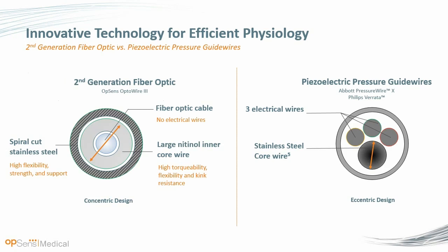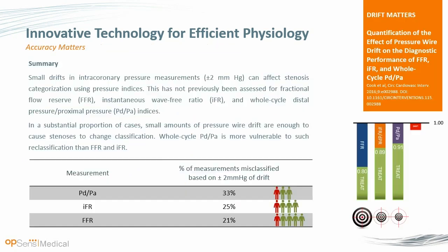And if you compare on the right on the piezoelectric, this is where there's 3 electric wire. So that's the reason why the piezoelectric wire is so stiff. It's because there's 3 electric wire and a stainless steel core in the middle. So it's not built as a regular wire compared to the OpSens wire, which is really fiber optic in the middle, large nitinol core around, and a stainless steel spiral cut around also. So this concentric design gives really a good feel to the wire compared to the other piezoelectric pressure guide wires such as Abbott and Philips.